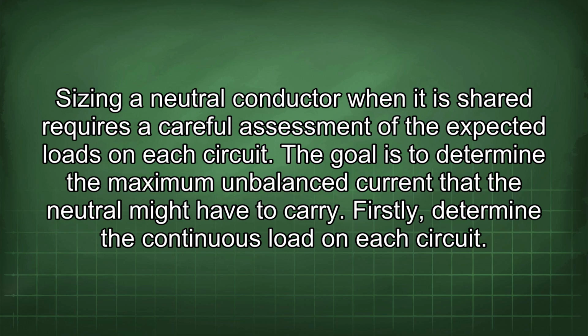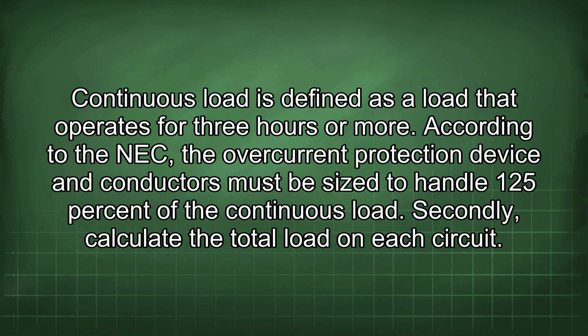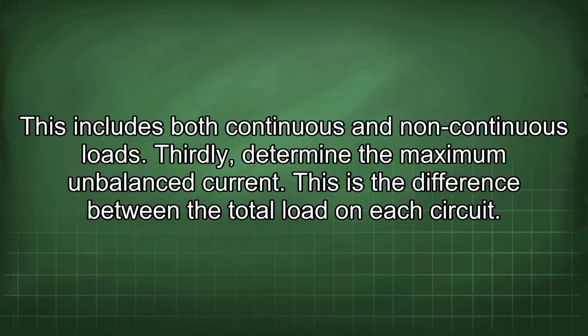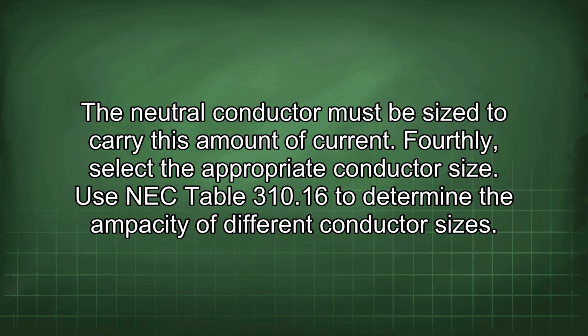Sizing a neutral conductor when it is shared requires a careful assessment of the expected loads on each circuit. The goal is to determine a maximum unbalanced current that the neutral might have to carry. Firstly, determine the continuous load on each circuit. Continuous load is defined as a load that operates for 3 hours or more. According to the NEC, the overcurrent protection device and conductors must be sized to handle 125% of the continuous load. Secondly, calculate the total load on each circuit. This includes both continuous and non-continuous loads. Thirdly, determine the maximum unbalanced current. This is the difference between the total load on each circuit. The neutral conductor must be sized to carry this amount of current.